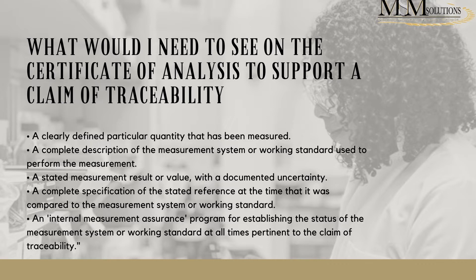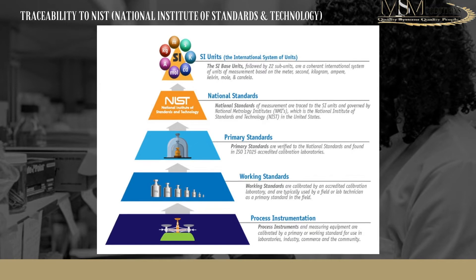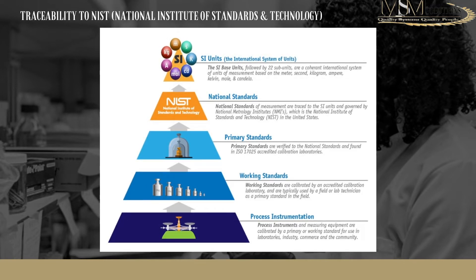When you look at your CRM, you will see that it will say traceability to NIST — the National Institute of Standards and Technology. At the top we have SI units; there are international SI units followed by 22 subunits. Your SI units include kilogram, mole, second — all the different measurement parameters have an SI unit that is then subdivided. From this you have the National Institute of Standards and Technology, and from that traceability you will get your calibration labs or certified producers who would prepare primary standards. From these primary standards, working standards would be prepared, and from that you would have your process instrumentation, your day-to-day runnings, giving you your traceability. Traceability is not only to NIST but essentially to SI — to a national or international standard.